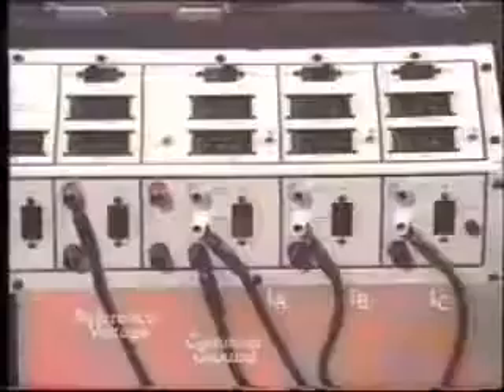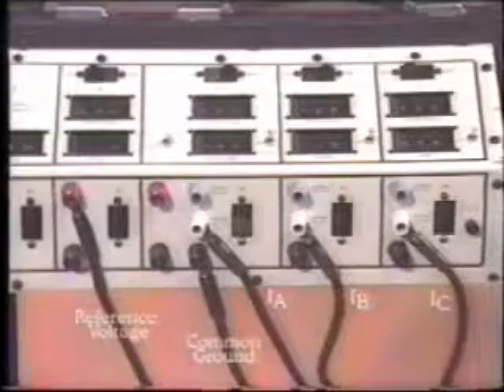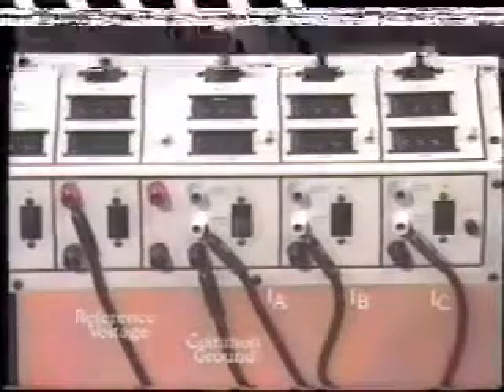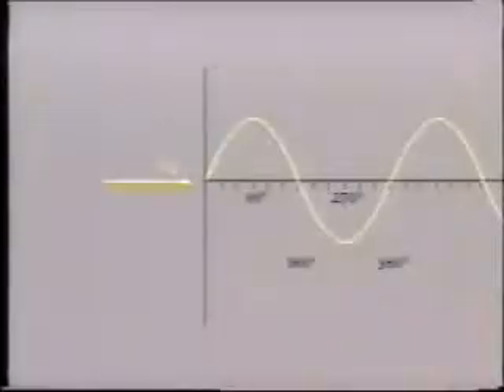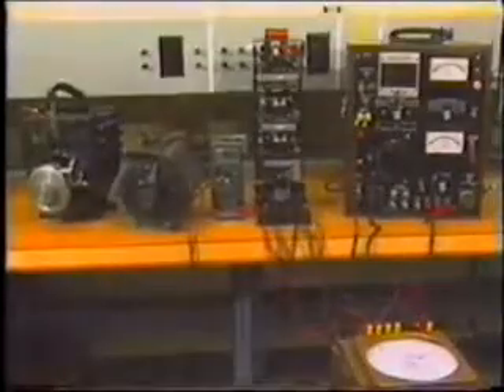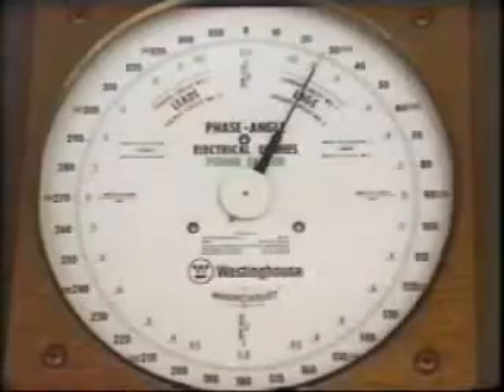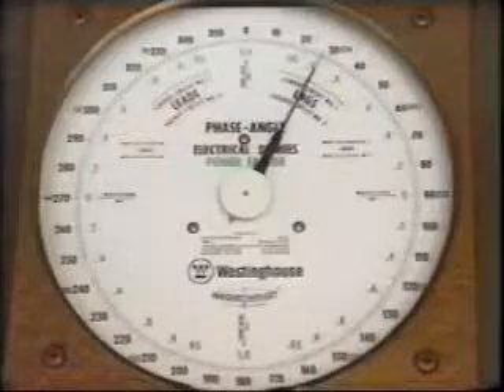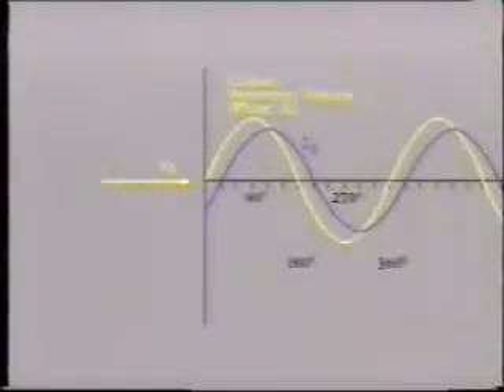Let's look at a simple example. Here we are trying to check the phase angle difference between current and voltage, and also to check that phase rotation is correct. Our reference voltage is connected to circuit 1. As this is from the A phase, it is indicated on our phasor diagram as VA. Now, using the correct test plugs, current IA is connected to the circuit number 2 on the instrument. The phase angle is measured and shown as plus 333 degrees. So the current IA can be plotted like this on our phasor diagram. You can see that the phase angle between current and voltage is actually 27 degrees lag.